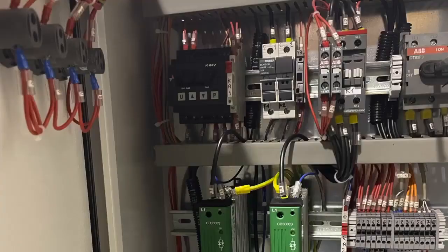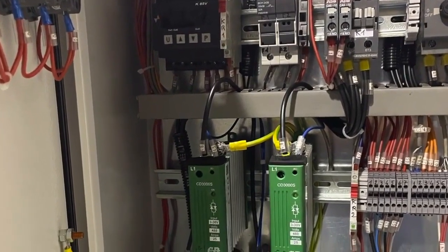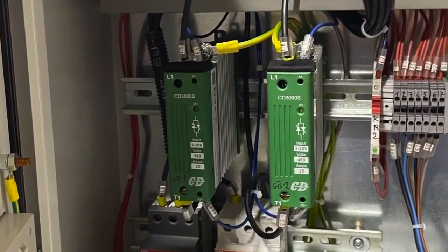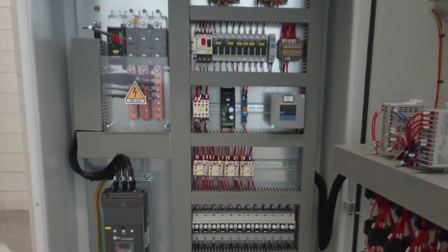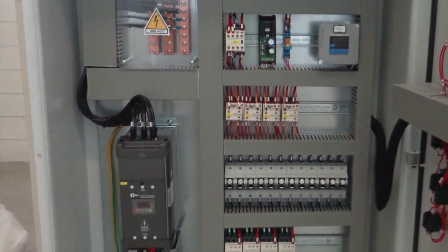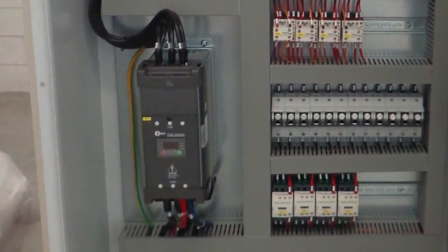In the past, machines with multiple stages, machines with different heating stages, were simply made, and I would modulate the power of the resistors through teleswitches or on-off static relays. So my proportional band thermostat would activate and deactivate, so to speak, the electrical load in order to maintain the temperature. The thyristor, or modulating static relay, enables me to modulate the power and provide the actual power required to maintain the temperature within the proportional band, and as a result, maintain the set point.